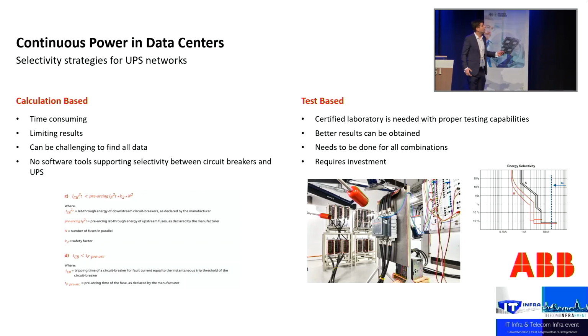Other option is to do the test. So you need, of course, a laboratory, the certified laboratory, where you can conduct this kind of tests. You can obtain better results, of course. You can have maybe higher breakers selected downstream of the UPS. And of course, there are many combinations, and this requires investment. So this is, I would say, a better solution, but of course, it's a bit more challenging.